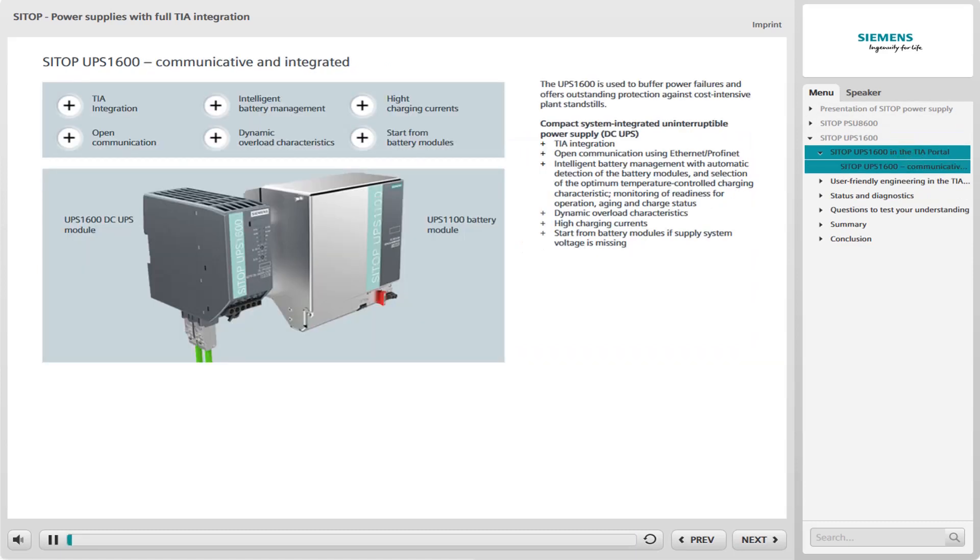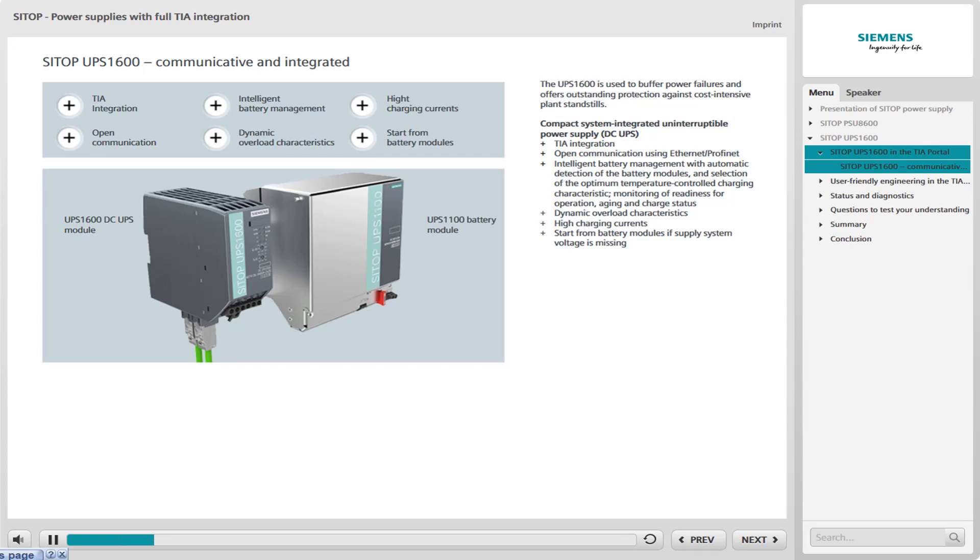A power failure means not only the failure of the 24 volt power supply, but also a failure of the automation system. This results in cost-intensive outage times and undefined plant states. The UPS 1600 DC UPS module prevents such failures by supplying the 24 volts with the help of the connected UPS 1100 battery modules.